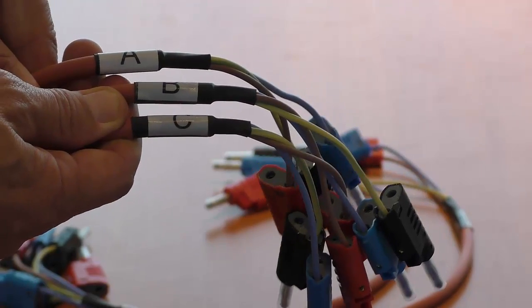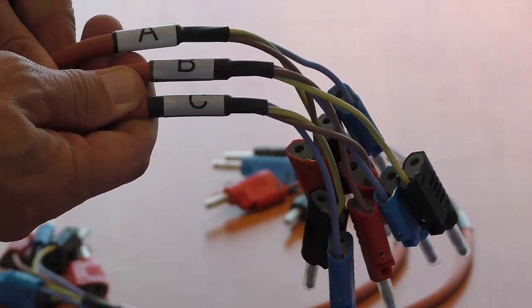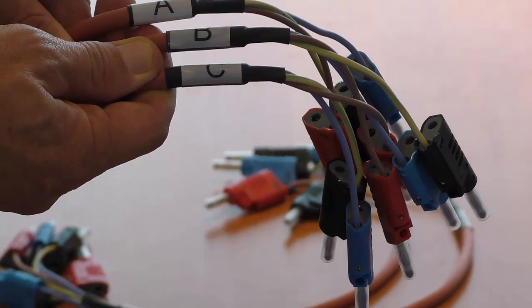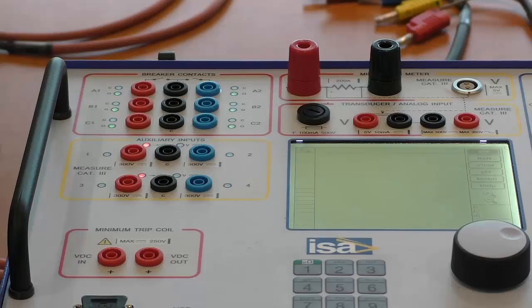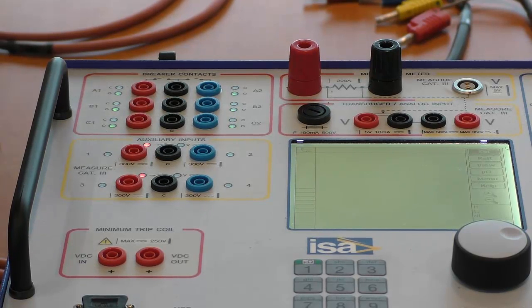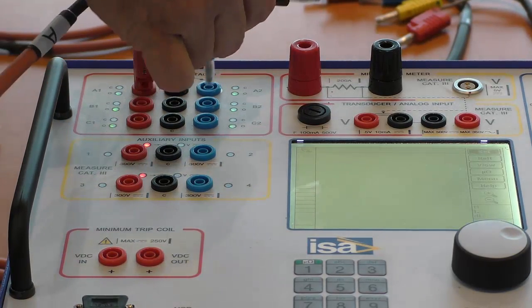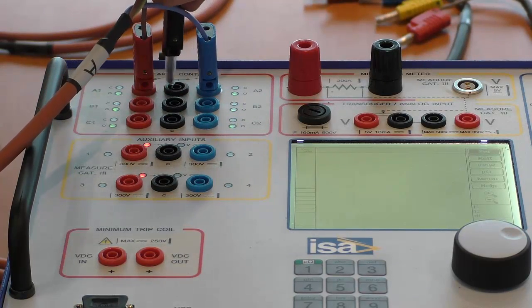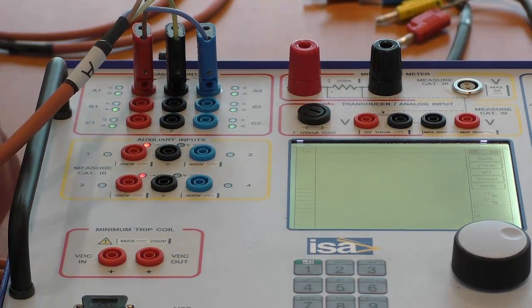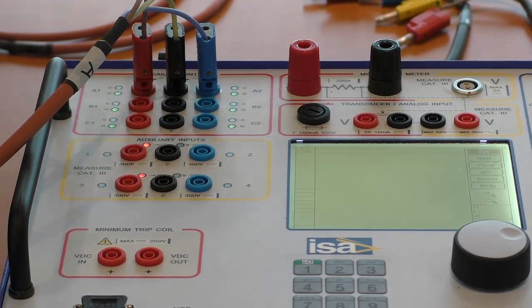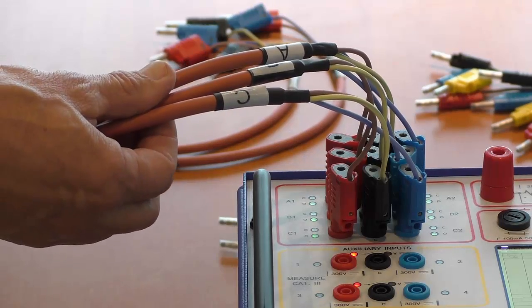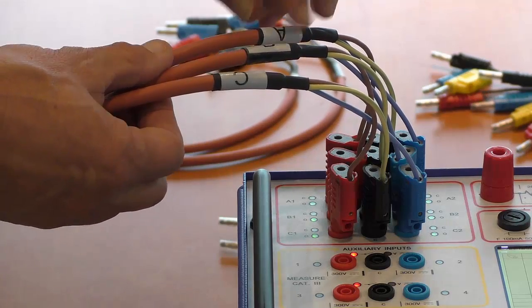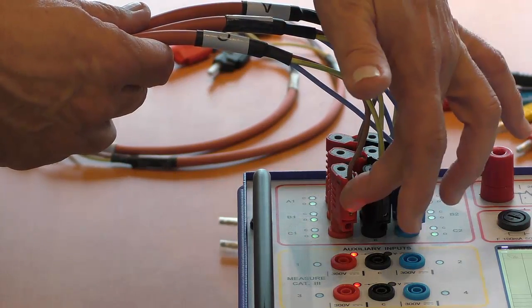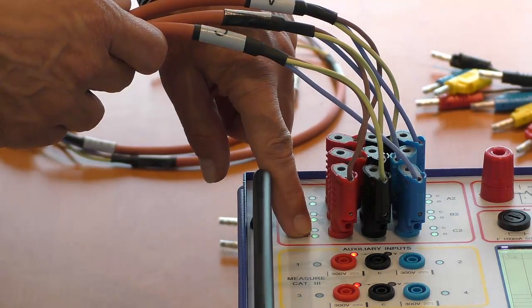To identify the main contact timing cables, find the cables marked A, B and C for the connection to the main contact timing terminals. For phase A, connect the main contact timing cables to A1 and A2, positioning the colors according to the color codes: red to red, blue to blue and black to black. Do a similar thing for phases B and C. Once all three phases are in position, you will have A, B and C according to the color coding on the main terminals A, B and C of the device.